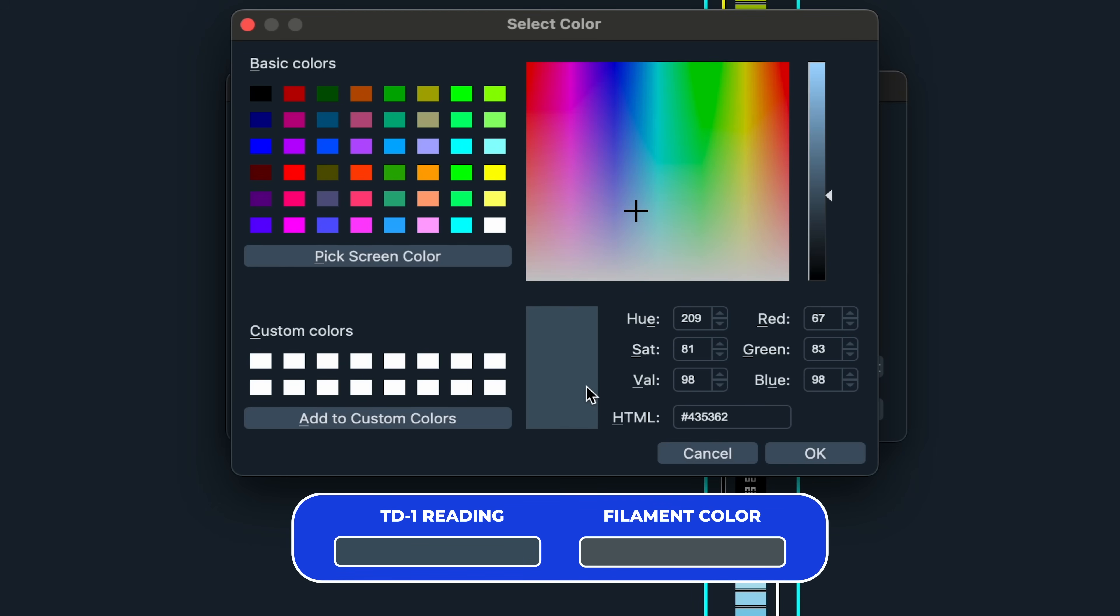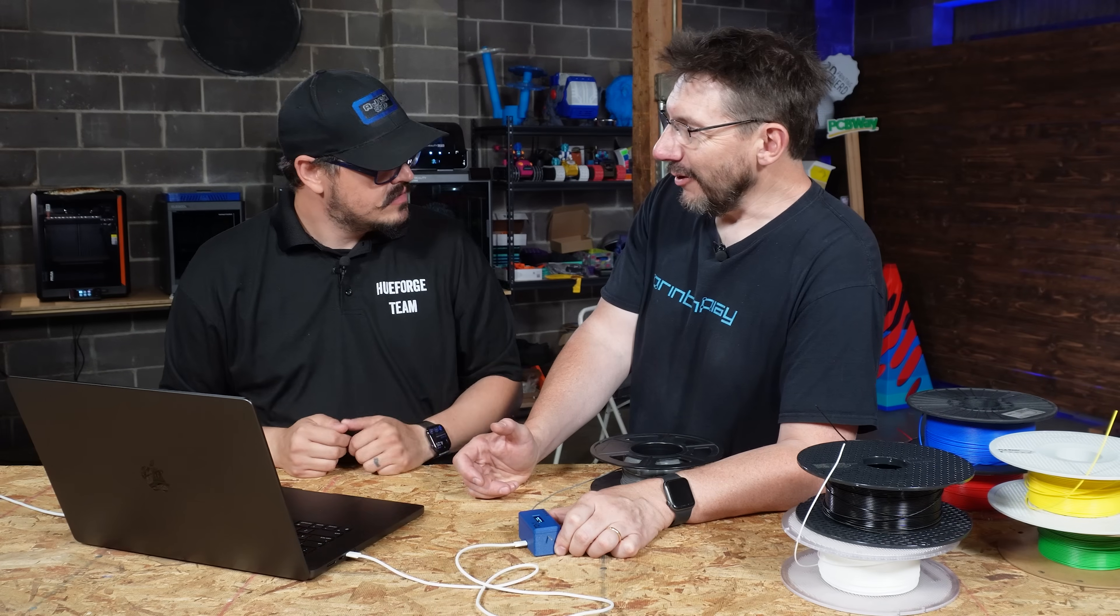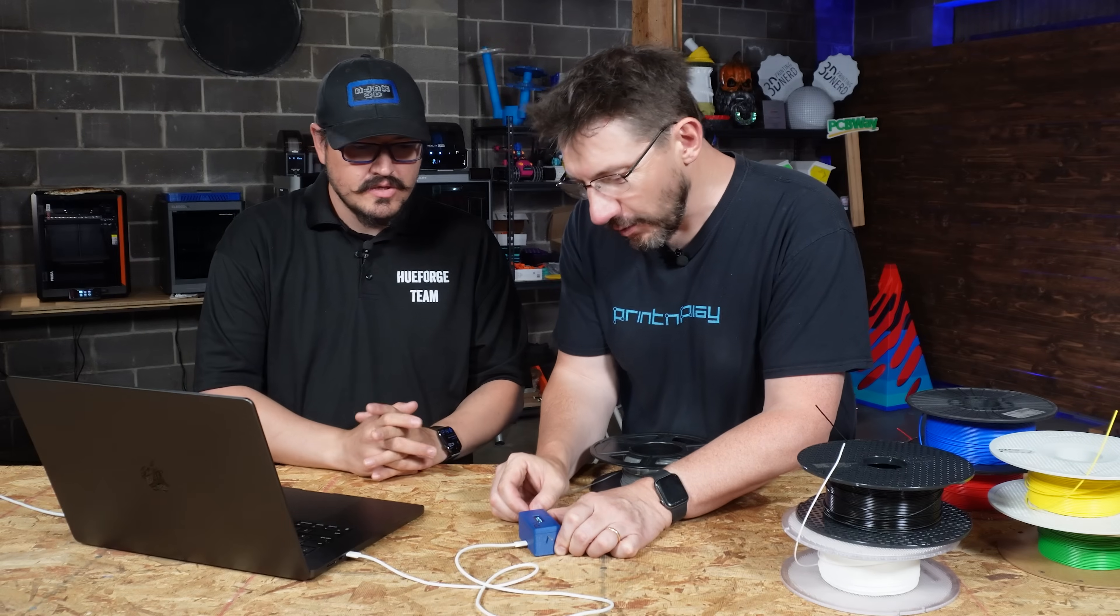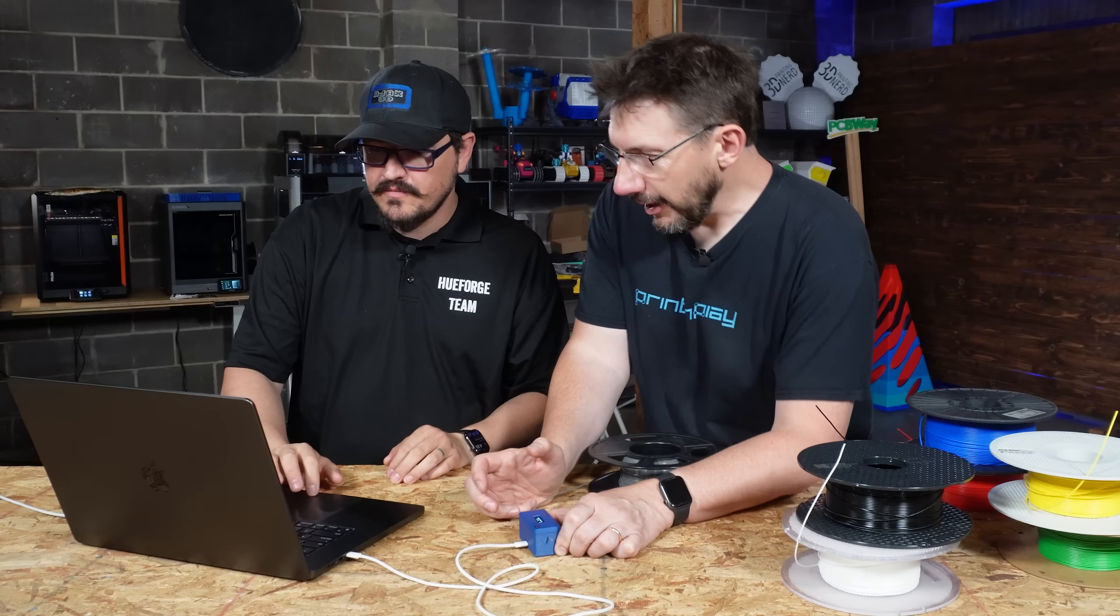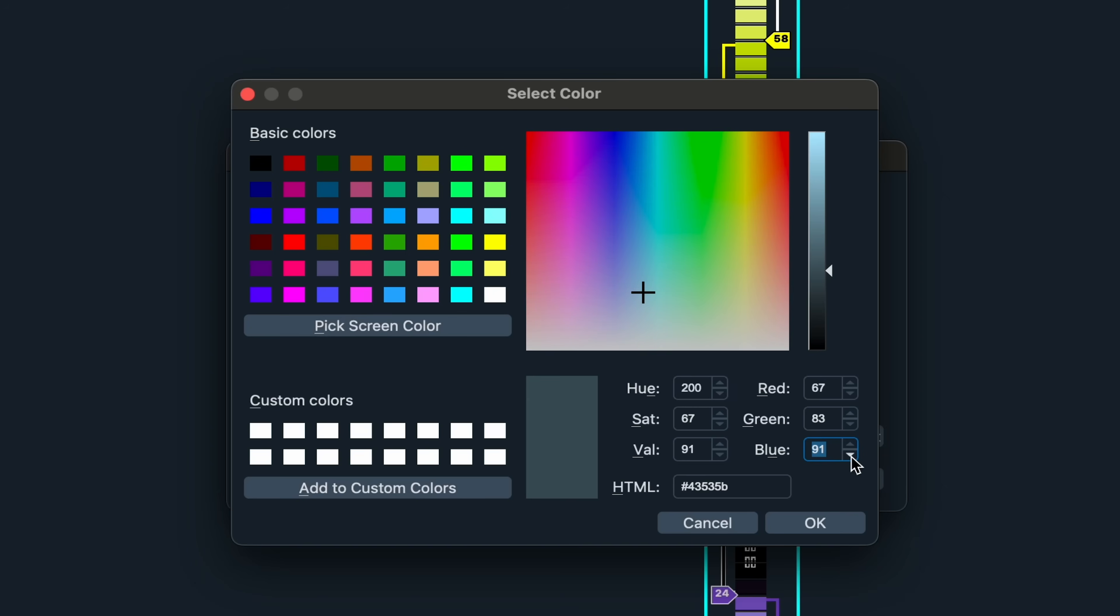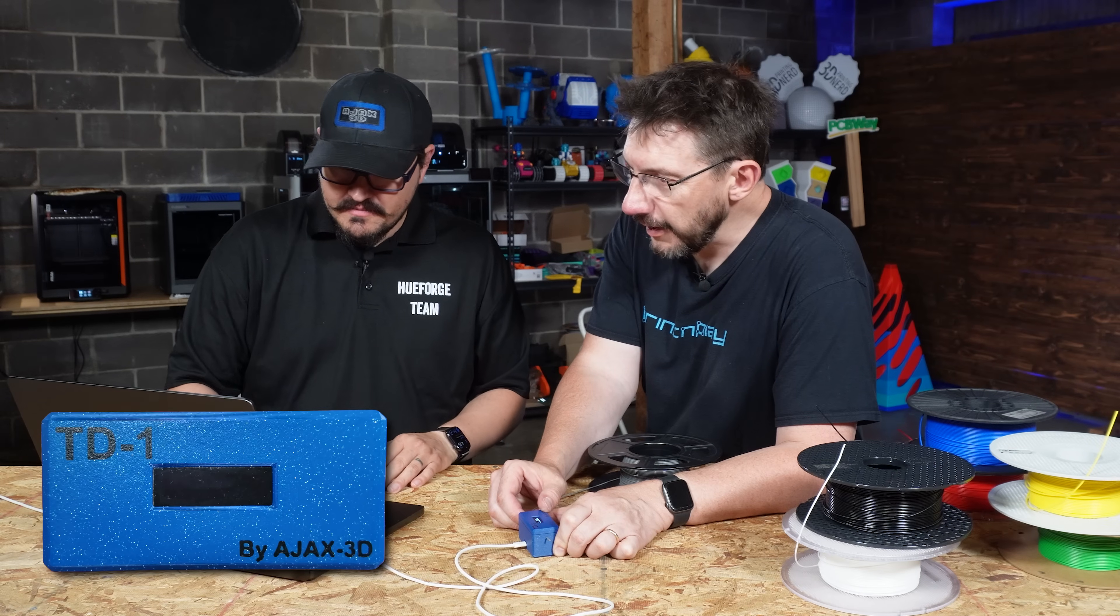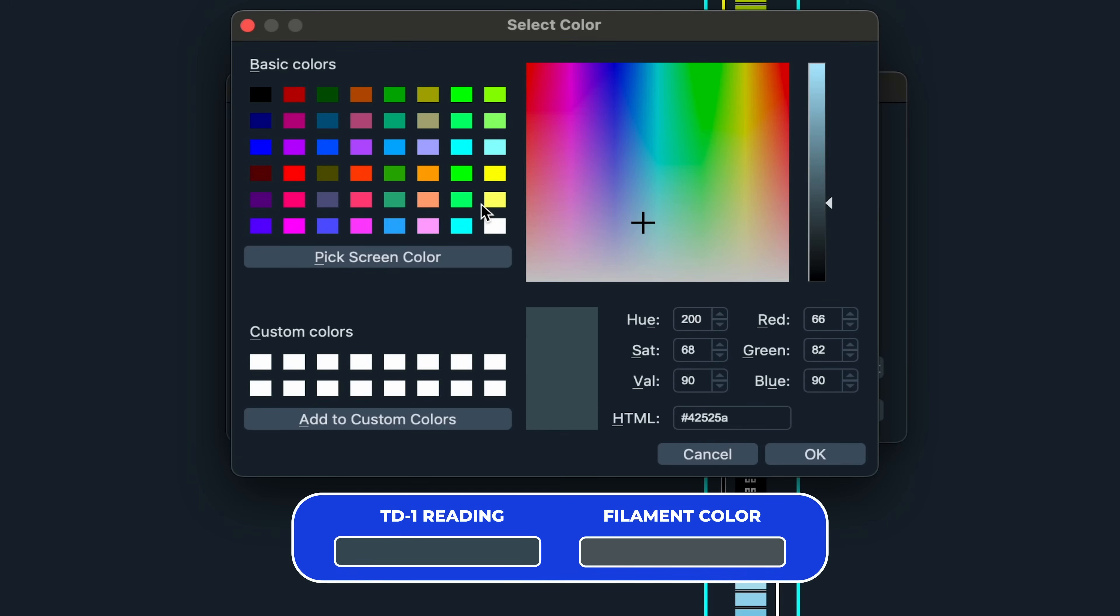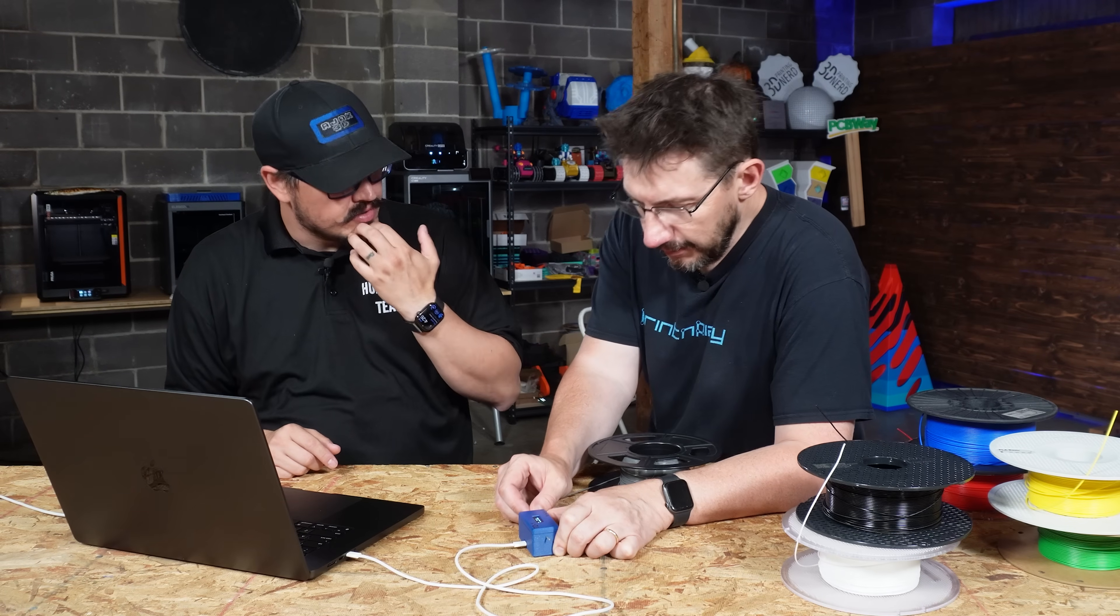So we double click it again. It's a little bit blue. We can just kind of bring blue down a little bit. This is cool. Yeah. Yeah. Okay. This satisfies the creative itch of my brain. I'm an artist. Okay. So we can leave this in for now. Okay. It actually does look to me to be a little bluish. Yeah. So I think I'm going to leave it at about 90. Okay. I think that's a good place to leave it. Sure. So we're going to hit okay. And then same concept here. We're going to apply. 42525A. And so if we open that up, we can see it's much closer to 90. Oh, it's much closer. So it's pretty much dead on where we just adjusted. Now we can move to like a blue or a red. So red. Yeah. Let's do red. Okay.